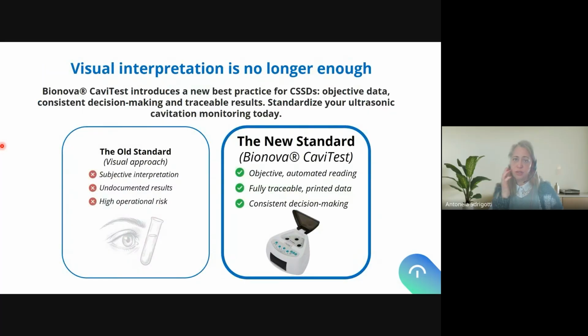So visual interpretation is no longer enough. And Bionova CaviTest introduces a new best practice for CSSDs: objective data, consistent decision-making, and traceable results. Standardize your ultrasonic cavitation monitoring today. So we have the old standard, which is the visual approach, where we have subjective interpretation, undocumented results, and high operational risk, while we offer the new standard, which is the Bionova CaviTest option, with objective automated reading, fully traceable printed data, and consistent decision making.